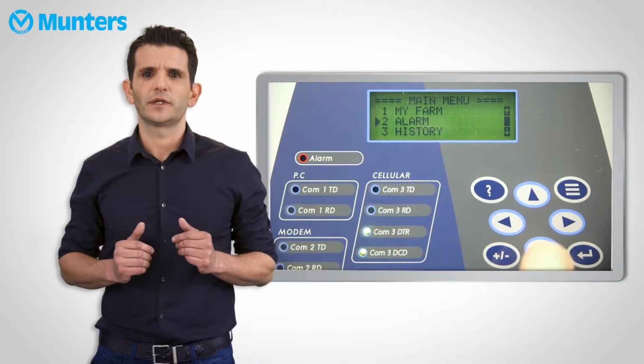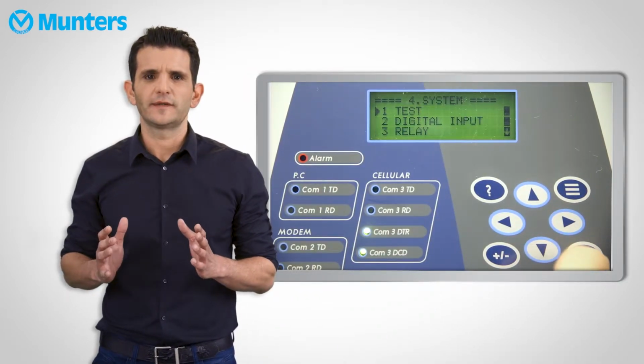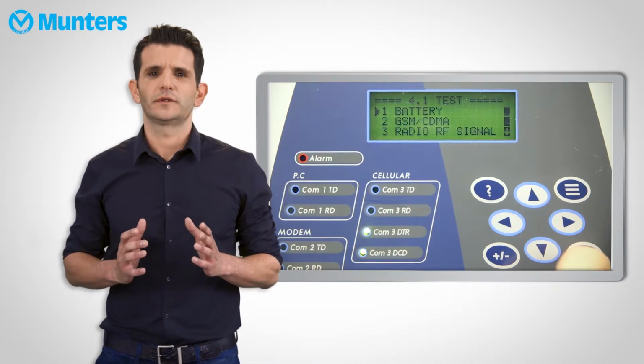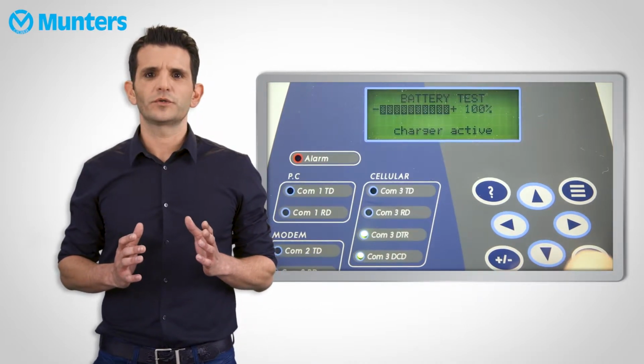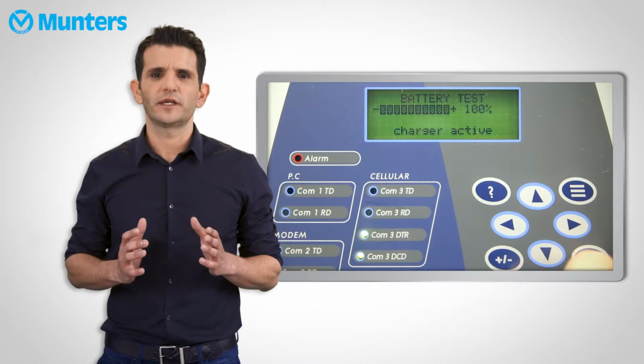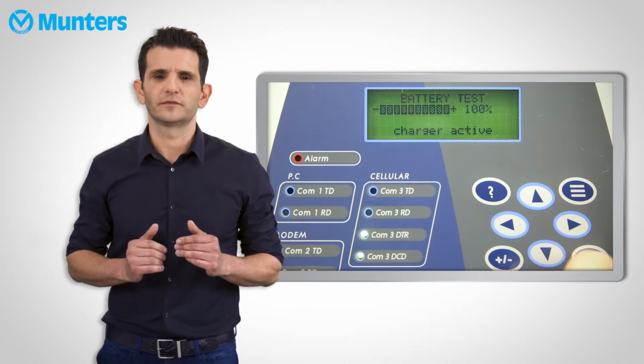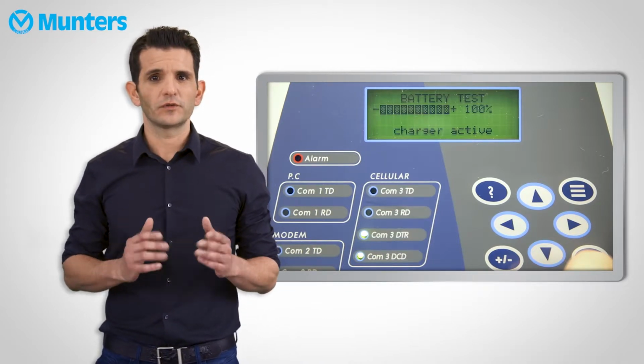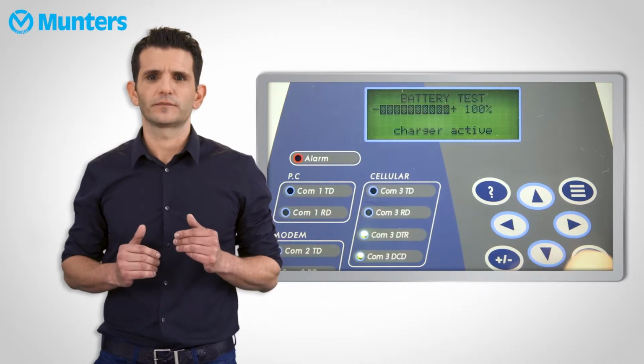In order to test the battery and the battery charger, navigate to System menu, then Test and Battery. This menu will show you the amount of battery life left and whether or not the charger is active. A faulty charger will also trigger an alarm in the communicator. However, this test is not enough, and we must make sure periodically that the battery has enough power to do the job when the power dies.